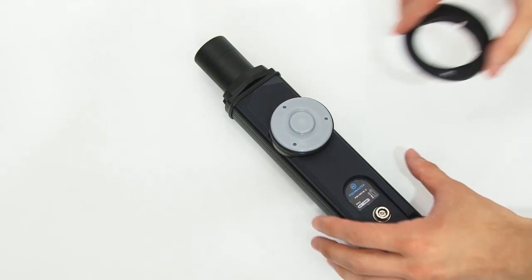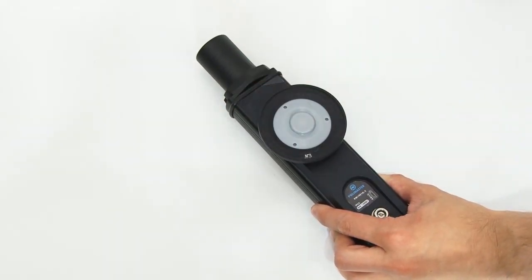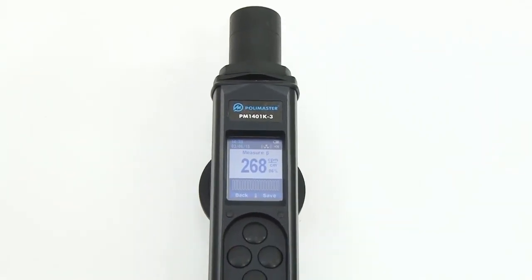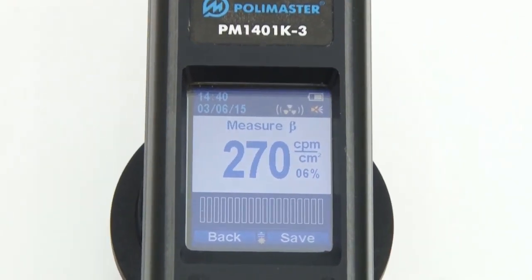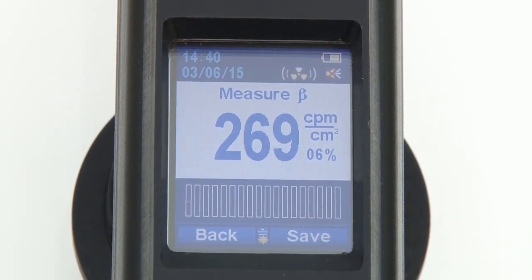Then remove the spacing rings and install the gamma-beta filter. Spacing ring number 3 is installed on the gamma-beta filter. Place the instrument on the inspected surface and press the next button. Now the instrument displays the value of beta radiation flux density. You can record it when the statistical relative error satisfies your needs.